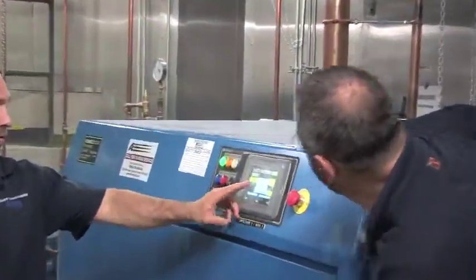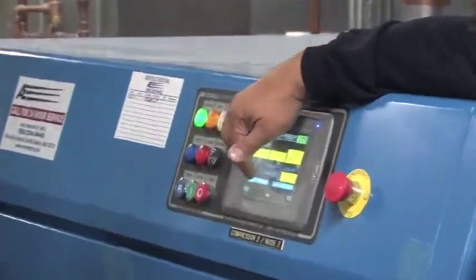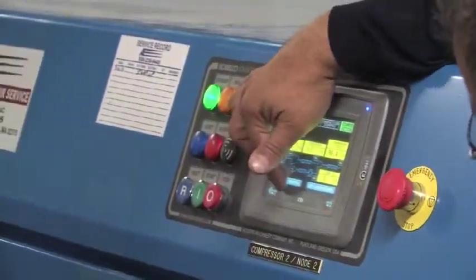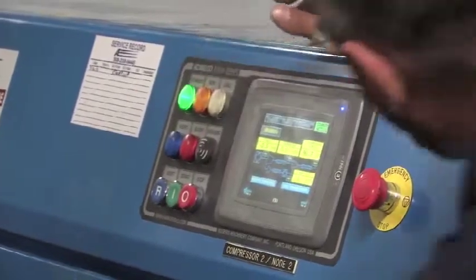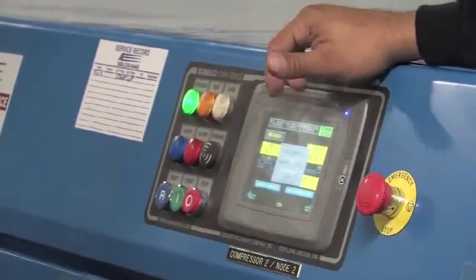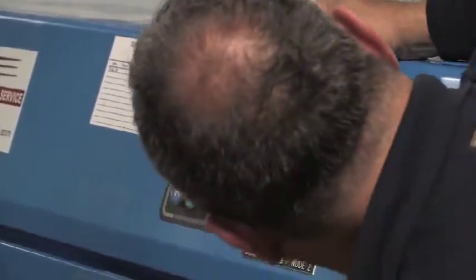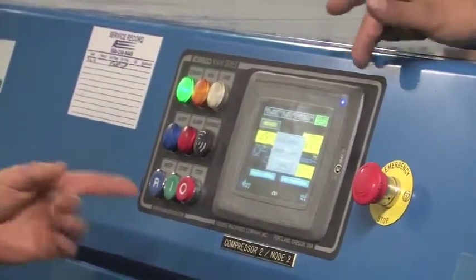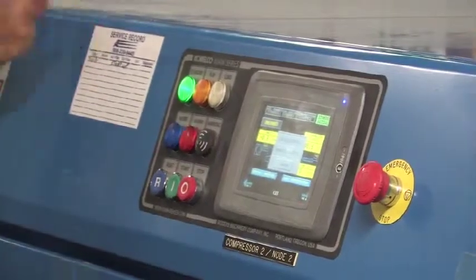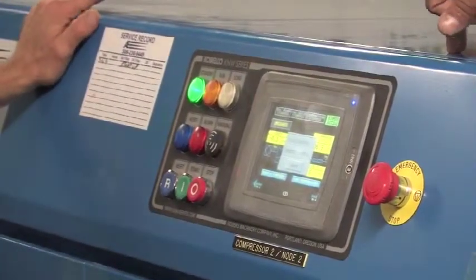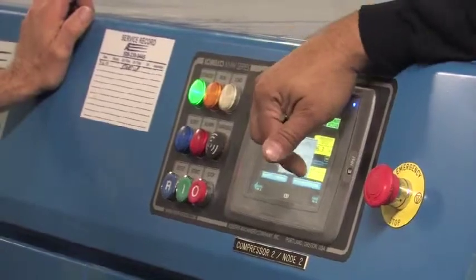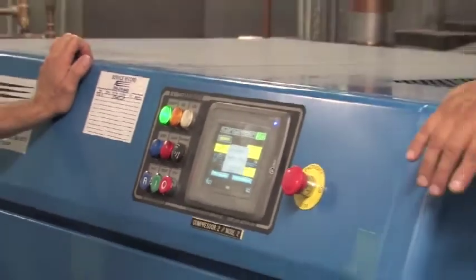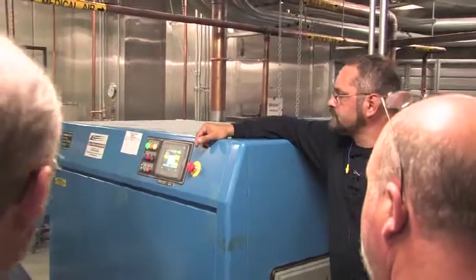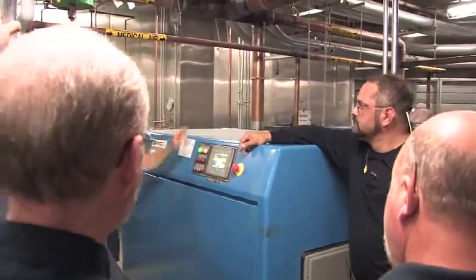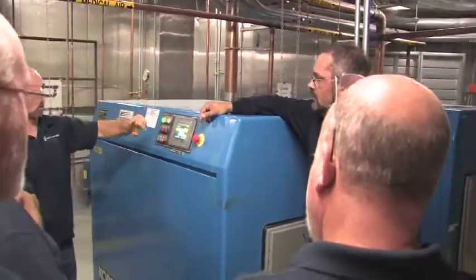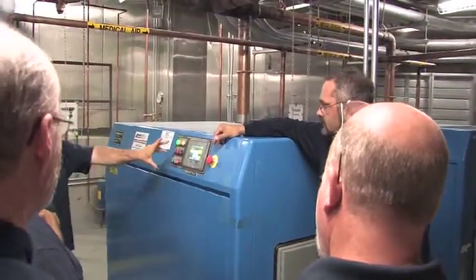Yep, exactly. You touch that remote button and a little screen comes up. And it asks you what you want to be in, remote or local. Remote is dealing with the master, so remote sends it back to the master. Local puts it in here. And once you put it in local, you can toggle the lead or lag. So if you take the master out, then you would have to put both of these in local control, and then you would have to determine which one you want to be the lead and lag compressor. Right, you yourself.